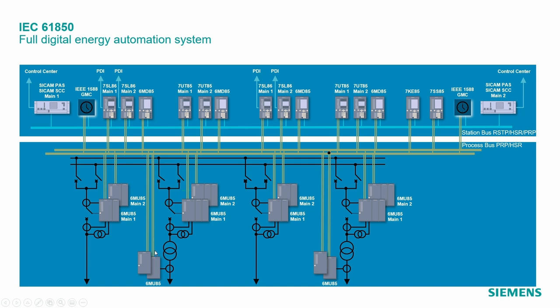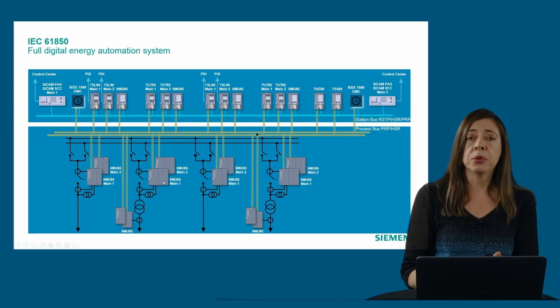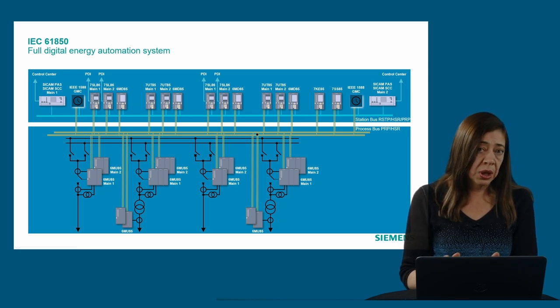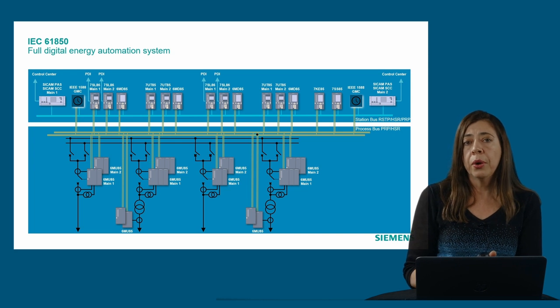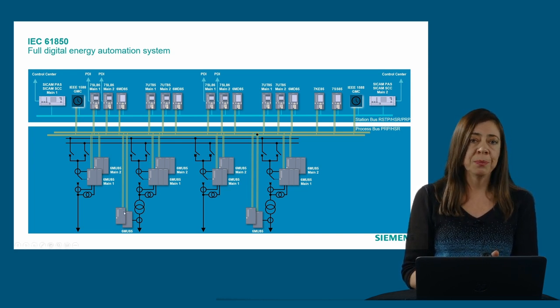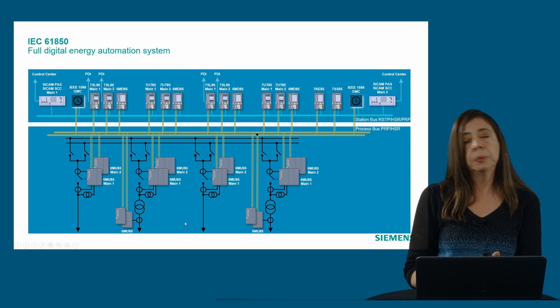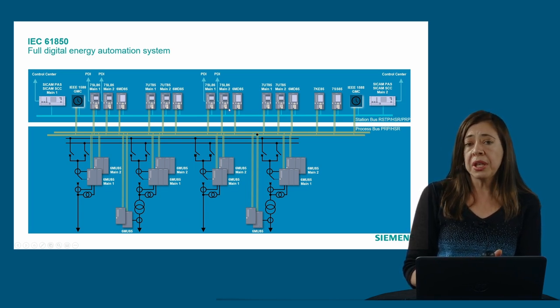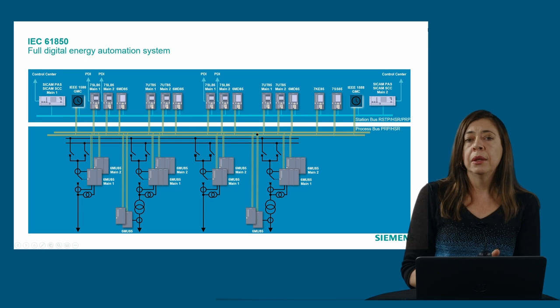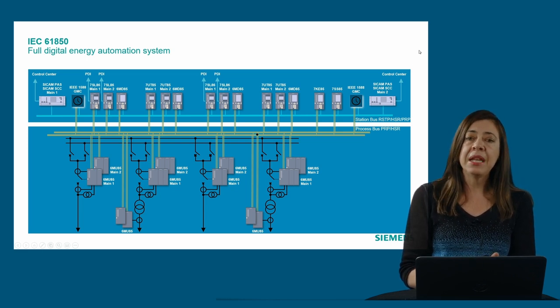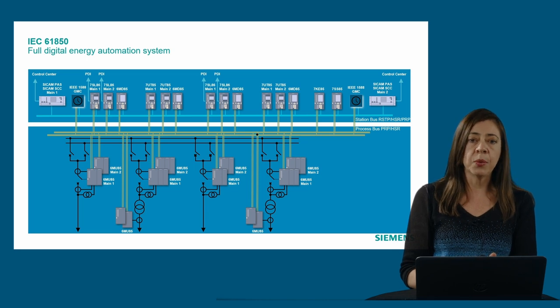In this case, for the transformer protection, if you, for example, use transformer protection as main and backup, then the recommendation is having also redundant merging units on the low voltage side of the transformer. If you use the transformer protection as main protection, but as backup only an overcurrent, then you will need only one merging unit in the medium voltage part. We are also showing here the separated station bus, and this is basically the diagram or the schematic from a complete digital IEC 61850 station.